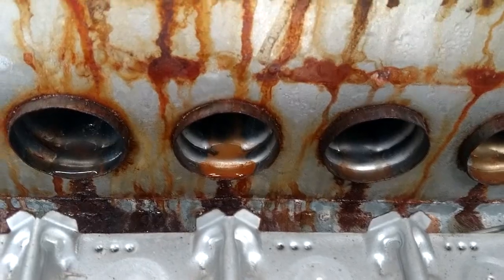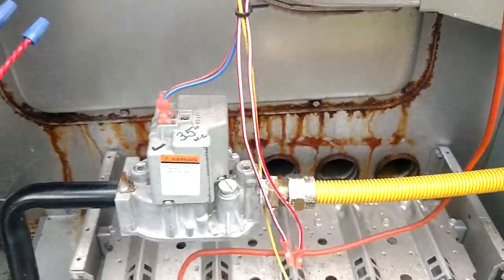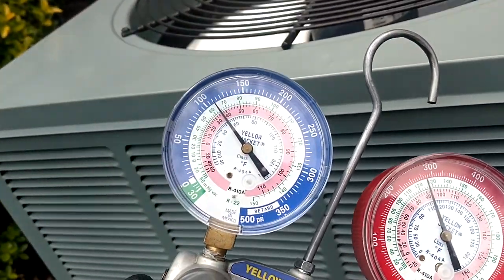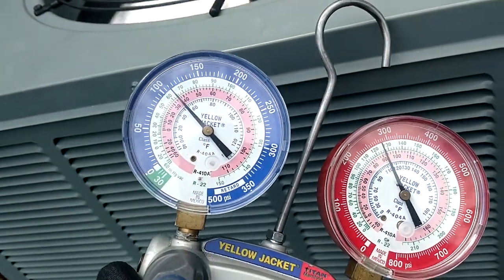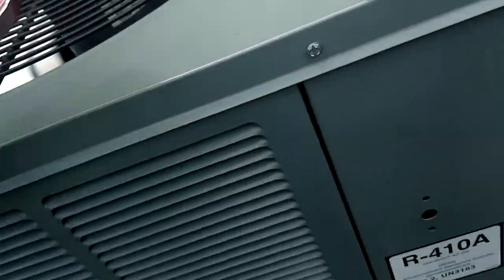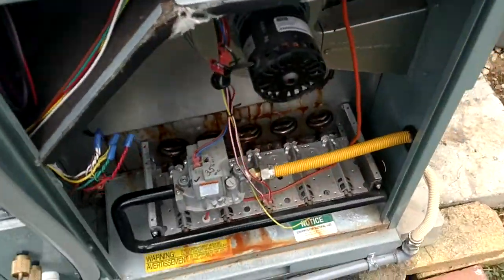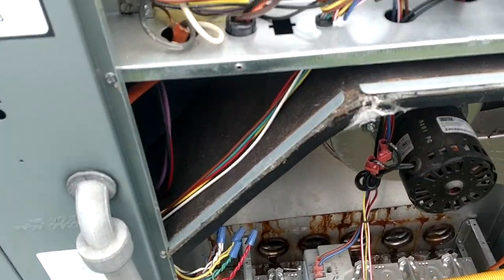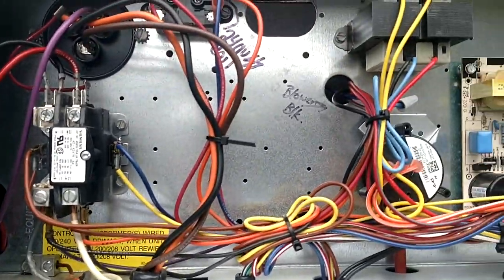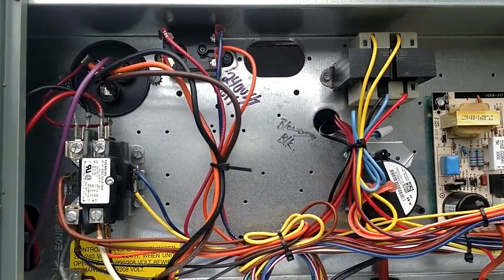Anyway, that's what we're looking at — puddles in there. Everything with the air conditioner is looking good, pressures are running good. People keep their house at about 75 degrees, filters are clean, and the unit's in real good shape. The indoor coil looks good.